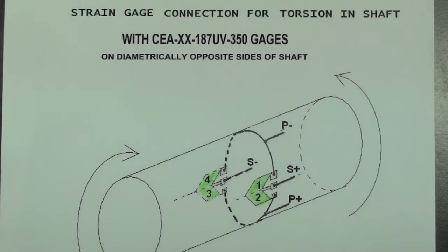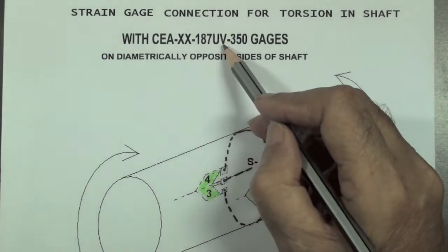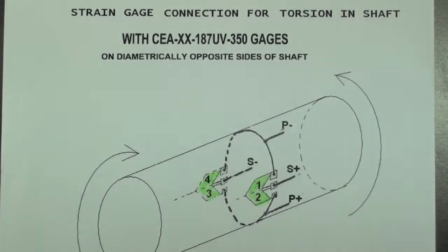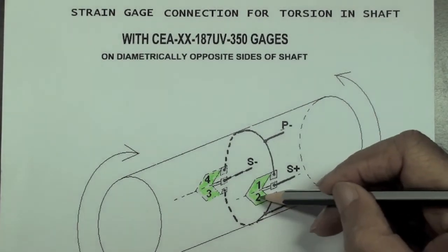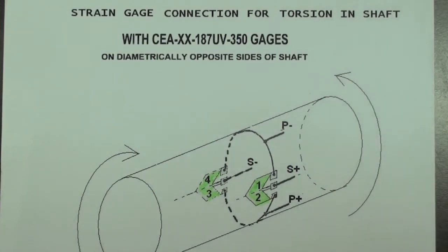For measuring torque in a cylindrical bar or shaft, a pair of shear gauges such as the micromeasurement's 187 UV gauges can be used. These are two element gauges with grid lines at 45 degrees to the long axis and they get aligned to the principal strains on the bar when it is subjected to torsion.